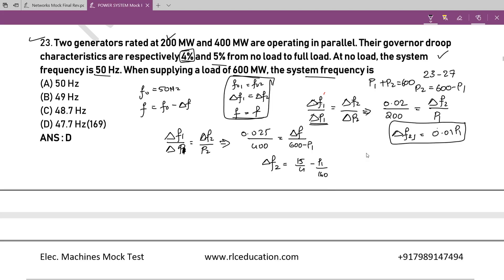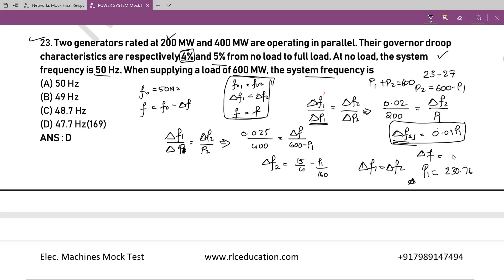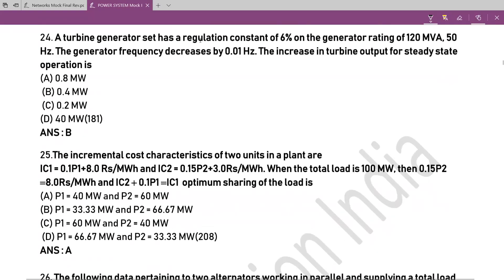With P₁ = 230.76 MW, the change in frequency is 0.01 × 230.76 ≈ 2.3 Hz. Therefore the final frequency is 50 − 2.3 = 47.7 Hz.